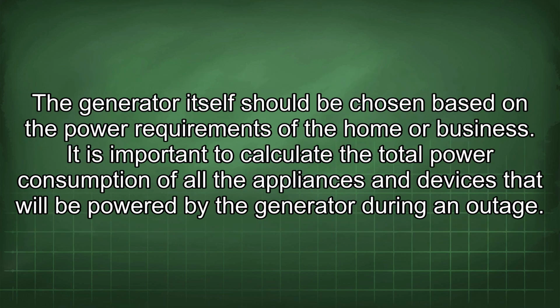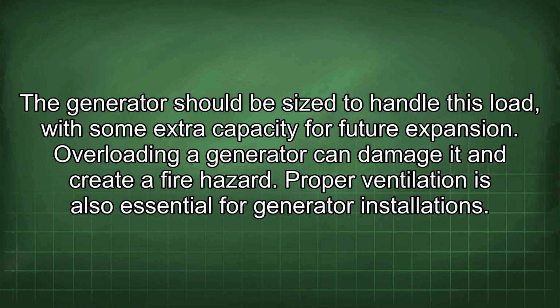The generator itself should be chosen based on the power requirements of the home or business. It is important to calculate the total power consumption of all the appliances and devices that will be powered by the generator during an outage. The generator should be sized to handle this load, with some extra capacity for future expansion. Overloading a generator can damage it and create a fire hazard.